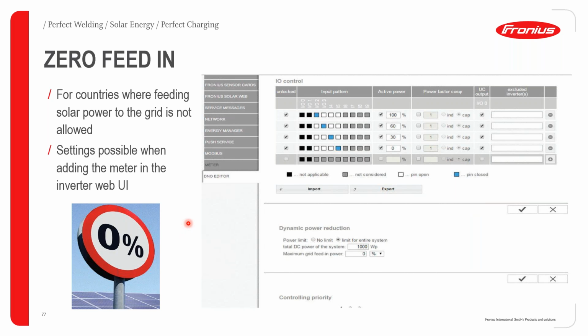So this is done when you're adding your smart meter in the inverter web interface or the configuration interface of the inverter. All you do is allow dynamic power reduction when you come to the digital or the DNO editor of the inverter interface. You say limit for the entire system, then you enter how much DC power you have installed in the system, and then you say maximum grid feeding, maximum is 0%. In this case, you are going to be feeding 0 power into the grid because we are doing a zero feeding kind of limitation here. So that is one very important use of the Fronius smart meter.